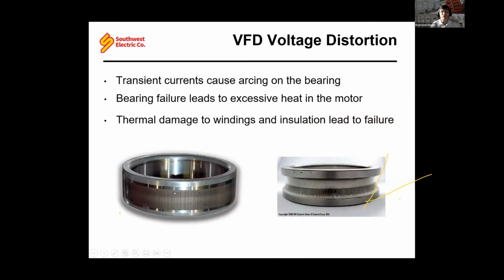Because of that distortion, these are some simple rolling bearings on motors. You can see that etching. If you would rub your finger along that etching, it would feel like a railroad track. That is the high frequency harmonics eating away at that bearing, and that obviously will lead to a bearing failure, which would eventually lead to a motor failure. You could end up damaging the windings, need the motor rewound altogether, or obviously at least replace the bearings.